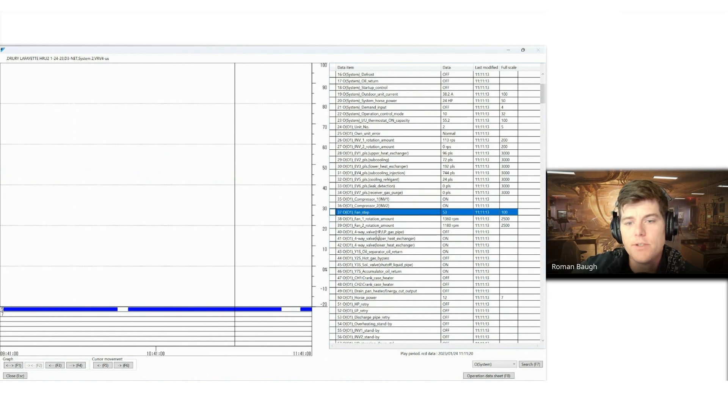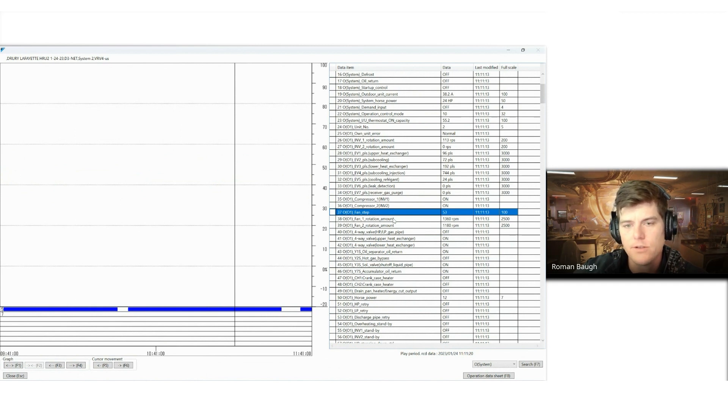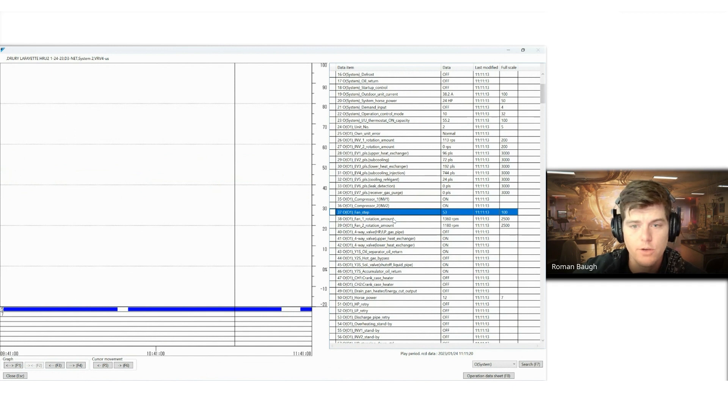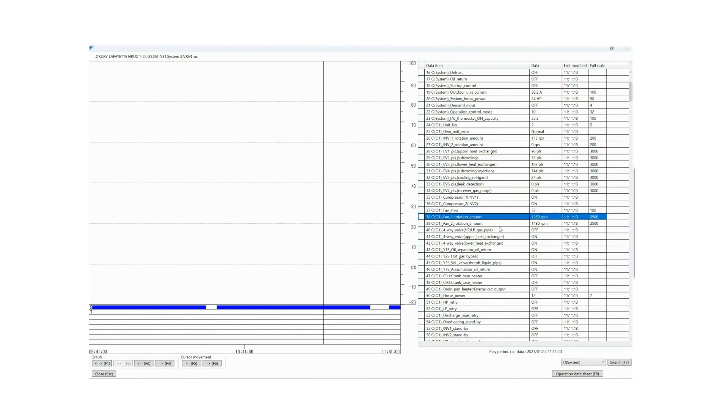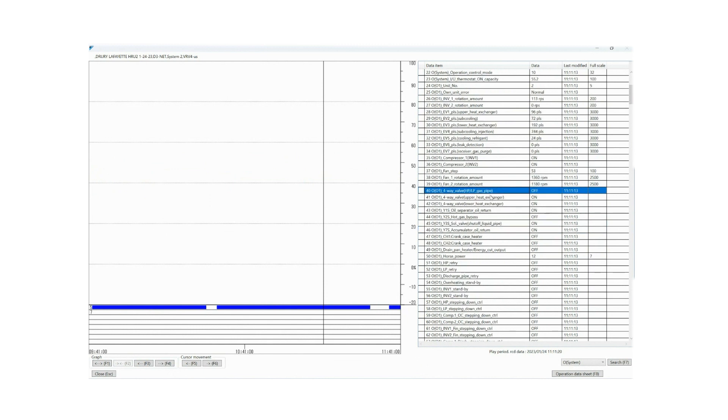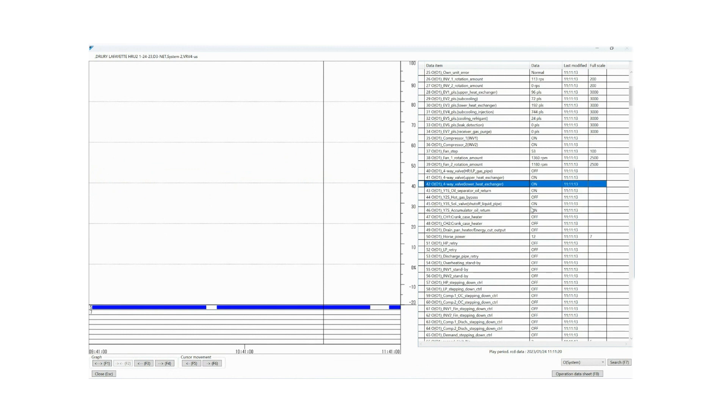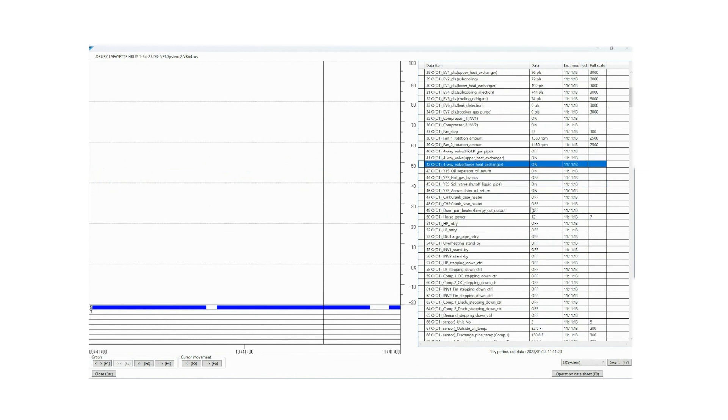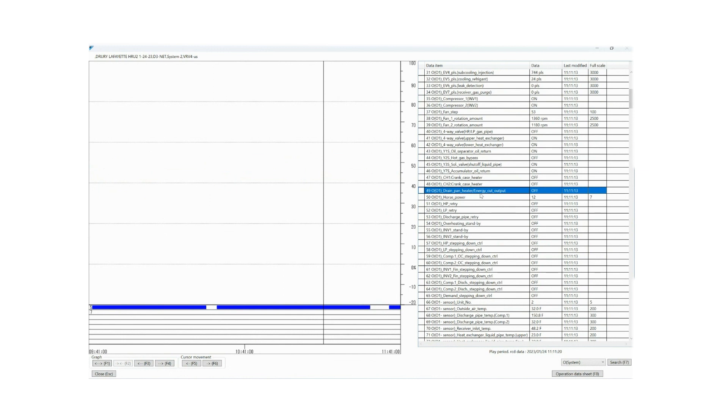So the fan steps, 0 to 53. You'll notice at VRV3, we were actually in a 0 to 8 step range, so it's a lot different. Just remember to always reference your service manual for the unit that you're actually working on. It goes a little bit further than just to say how many steps the unit has. The fan rotation amount for RPMs, first fan, second fan, so it's a dual fan chassis. Then your 4-way valves, high low pressure, upper heat exchanger, lower heat exchanger. These are all either off or on points. Hot gas bypass. These are all your solenoid valves in your outdoor unit. Then we get down here to crankcase heaters. We have drain pan heater energy cutoff. That's a new one, so I wouldn't really worry too much about referencing that one right now. Of course, power, we use that to measure how the system's performing in other markets.